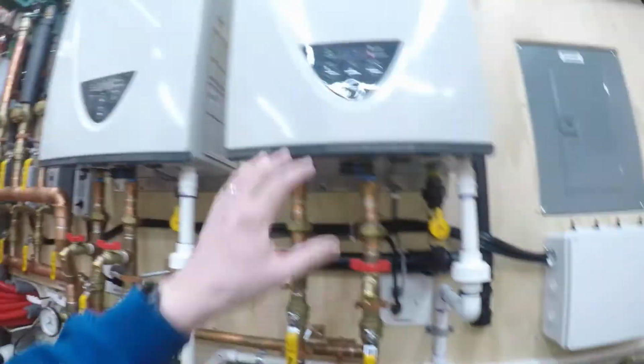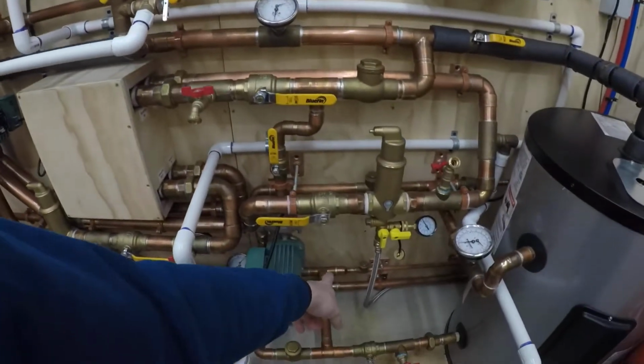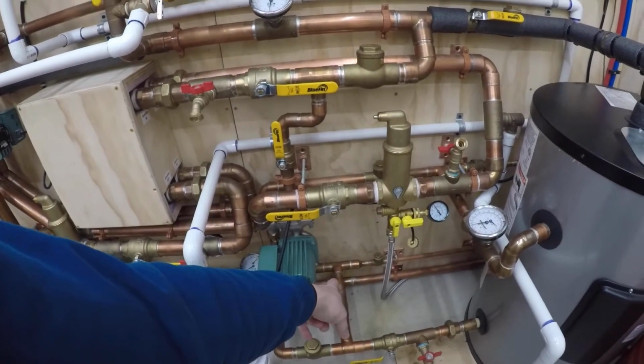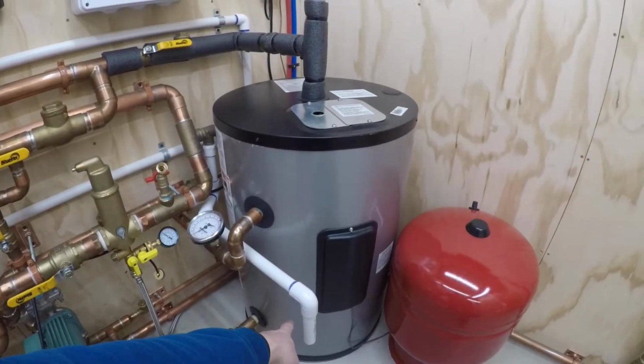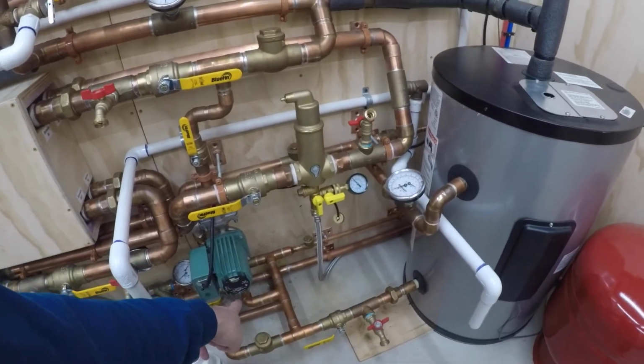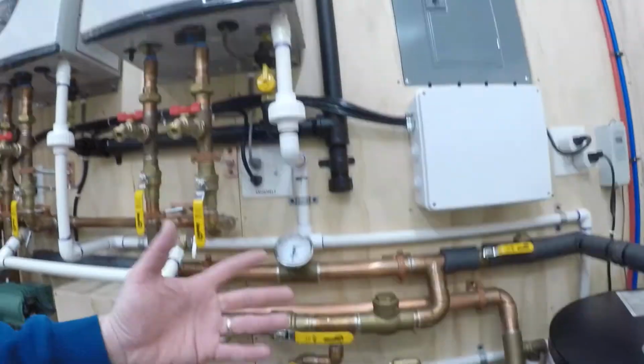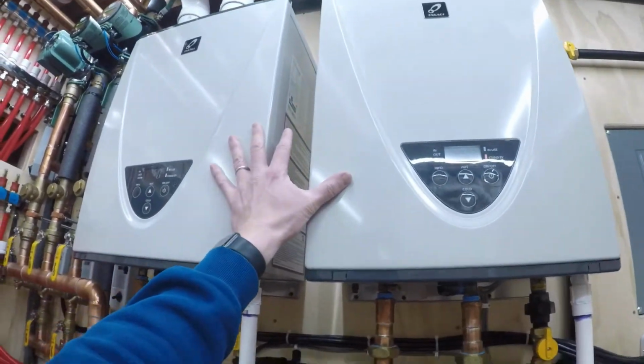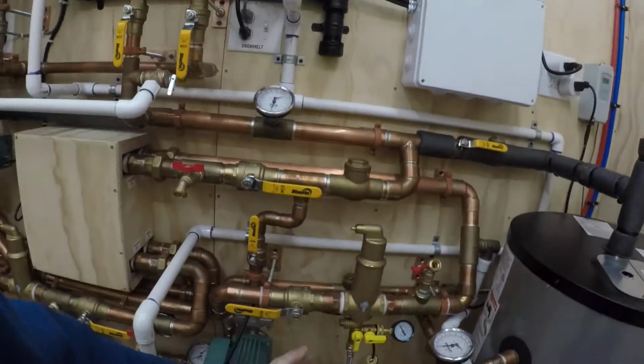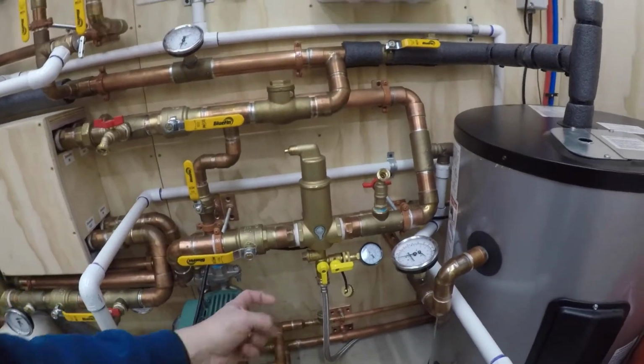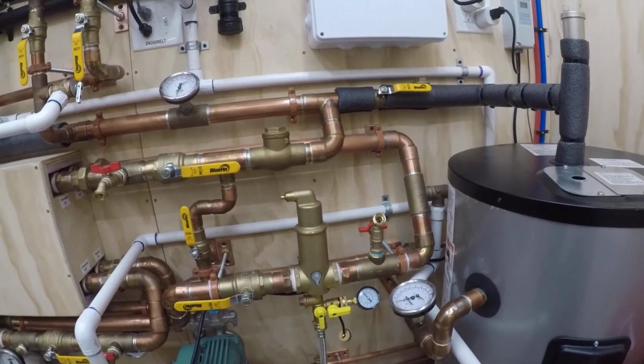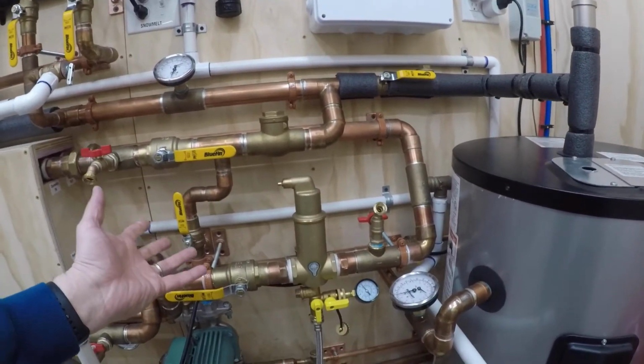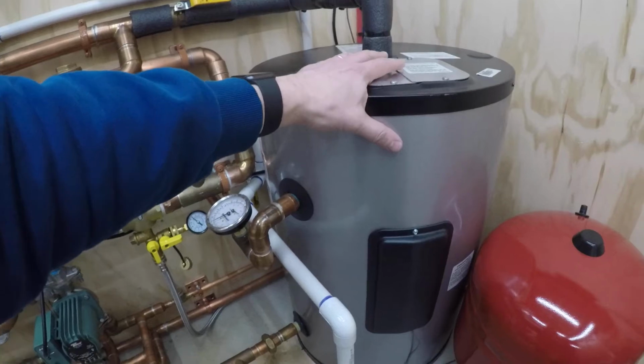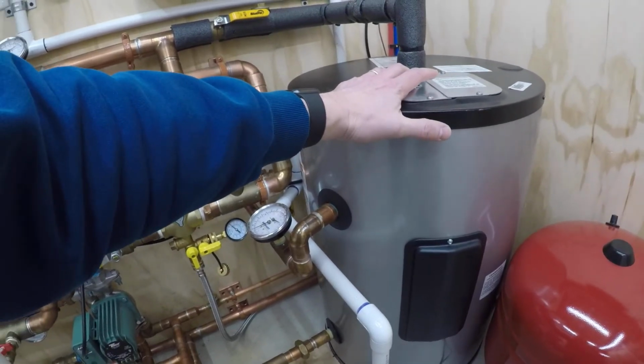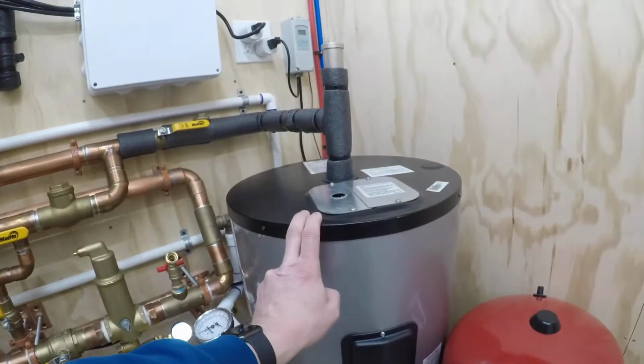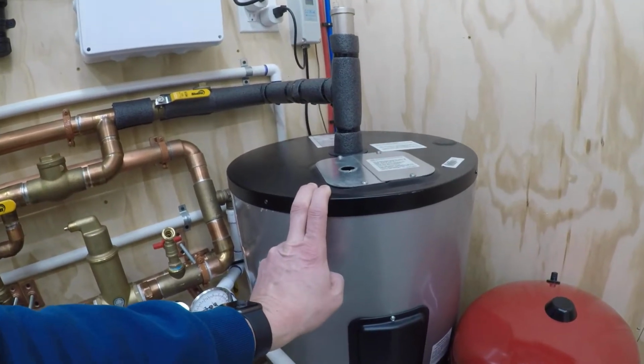So you will burn a little bit more BTUs because that water coming in from the street is 55 degrees. It's not 125 degrees like here, but it does mix together. And because you're pushing 7.6 total through both units and you're only pulling 2.8 in, you're only using 2.8 out the shower head, the remaining 4 or 5 gallons a minute comes from the tank. So even with the shower on, the pump will recirculate the tank to a point where it will shut off. It can catch up.